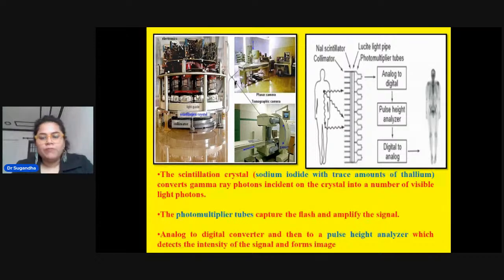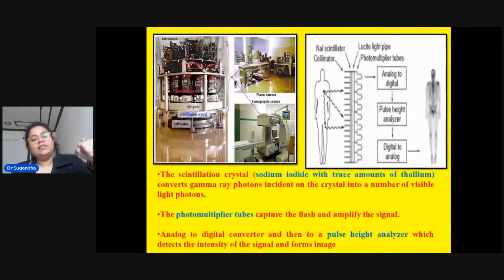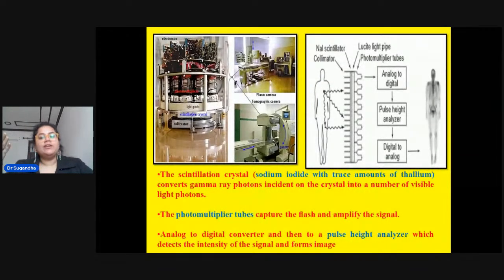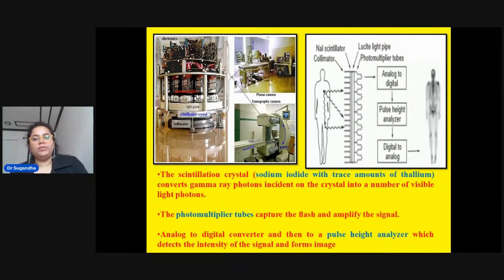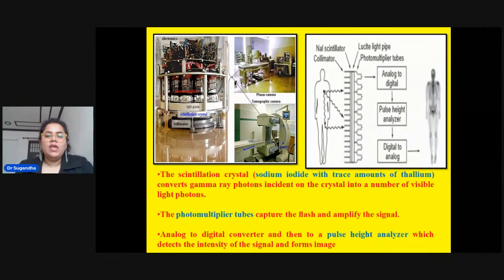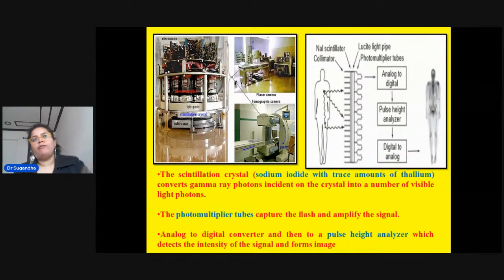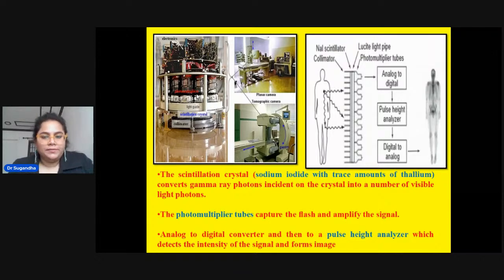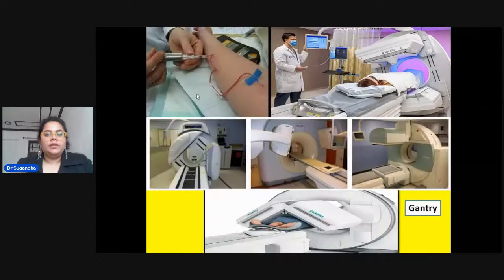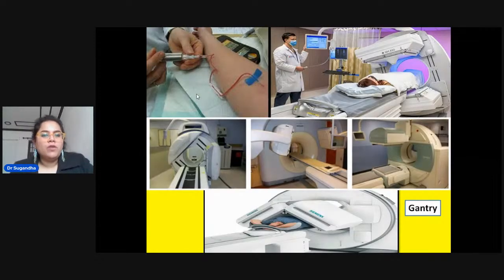The photomultiplier tubes capture flashes of light, amplify the signal, and convert it into a two-dimensional diagnostic image. The scintillation crystal is made of sodium iodide with a small amount of thallium. The crystal converts gamma rays into flashes of light; after amplification through photomultiplier tubes and a pulse height analyzer, the image is formed.